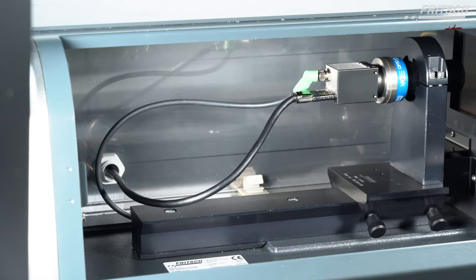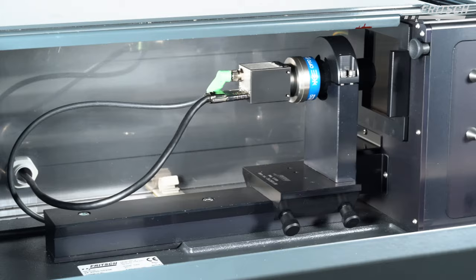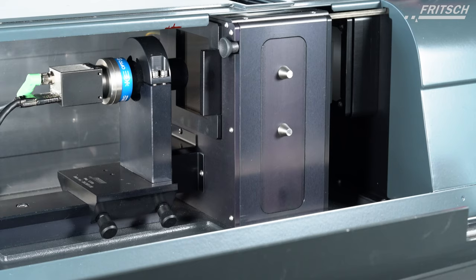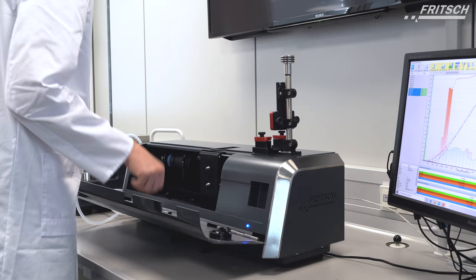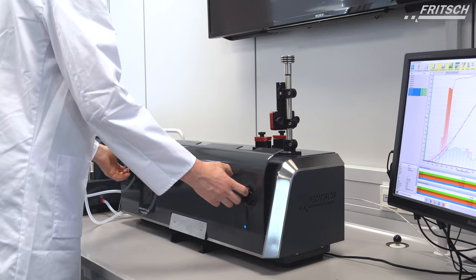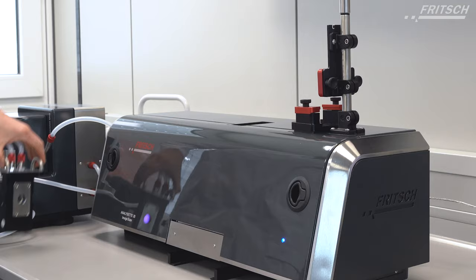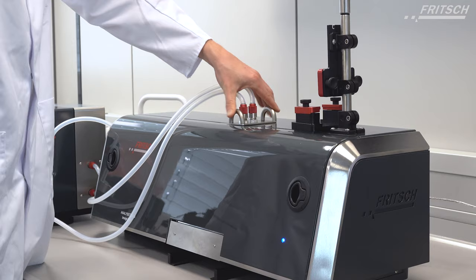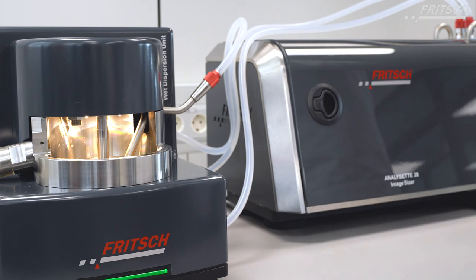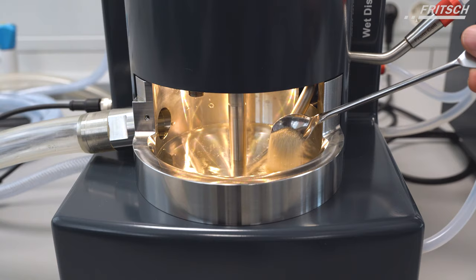Due to its special geometry, the measuring chamber of the ANALYSETTE 28 image sizer is automatically kept clean, so air flushing is not necessary. And nevertheless, if soiling should occur, it is fast and easily cleaned. For sample materials that are not free-flowing or even present as a suspension, the state-of-the-art Fritsch wet dispersion unit can be easily connected to the ANALYSETTE 28 and is automatically recognized by the software. The separate ultrasonic box can be utilized for further de-agglomeration of the sample.